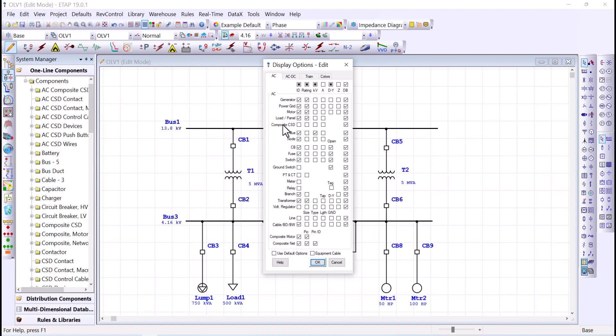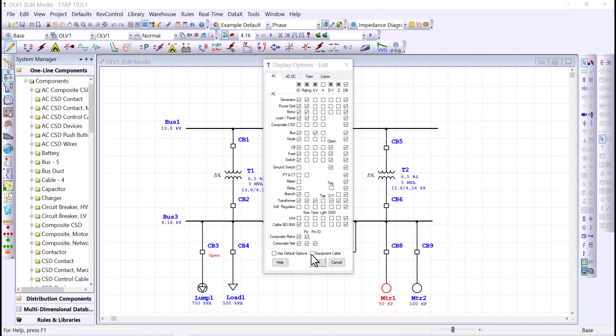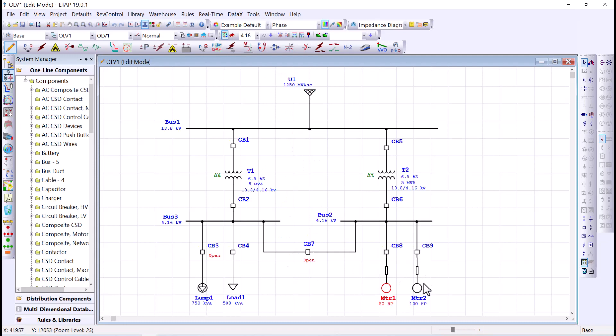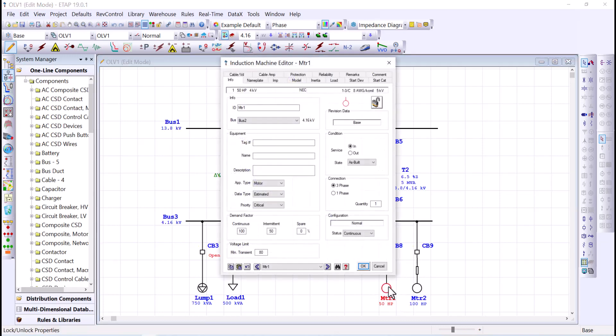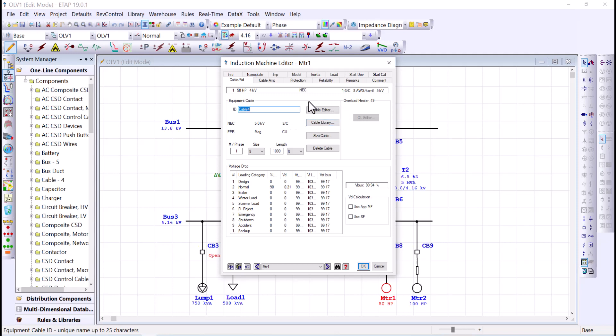For example, for a circuit breaker you can display the ID, rating, KV, and amperage. This section contains circuit breakers, fuses, and switches — you can display the off-normal status, meaning open position. The default setting for a circuit breaker is normally closed, so if you want to display breakers in an open position, check that box. Also, to display equipment cables, check that box — an equipment cable is a cable attached to equipment such as a motor, and these cables can be located in the load editor under the Cable/Voltage Drop tab.